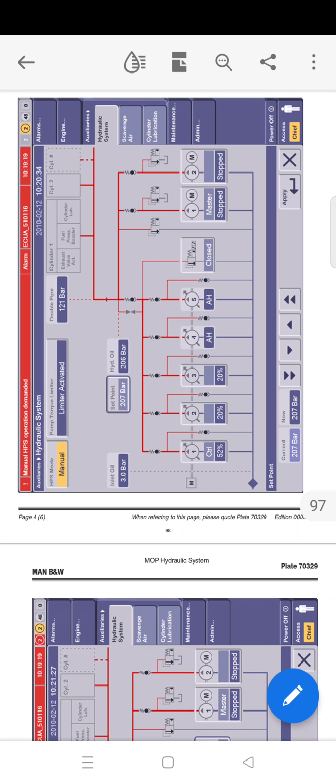Now operate the engine driven pumps bypass valve using either SU1 or SU3. The bypass valve is to be tested for movement every 6 months at a stopped engine condition. Start stop of the electric start up pumps. So you can do all these functions, guys. If for some reason automatic control of an engine driven pump cannot be maintained, the pump's swash plate is deflected to 100% in the full head direction only.